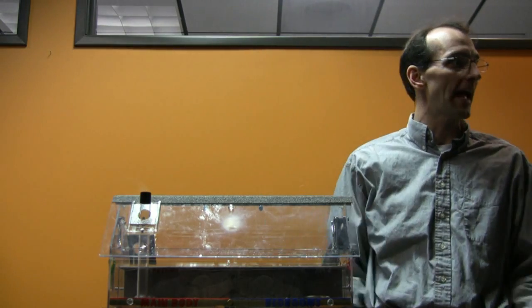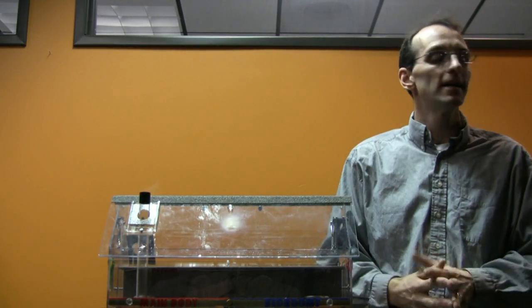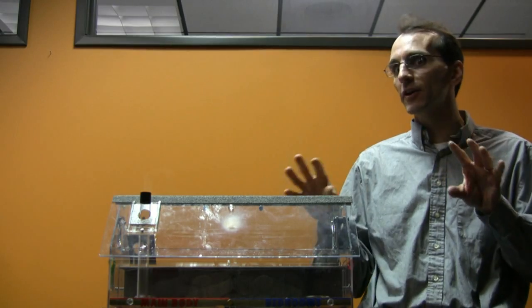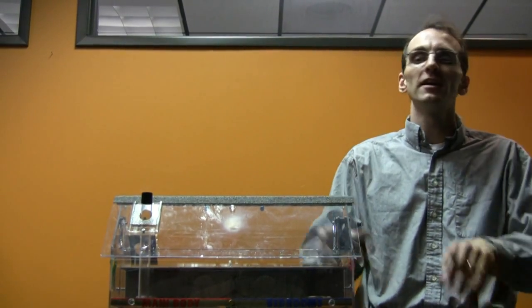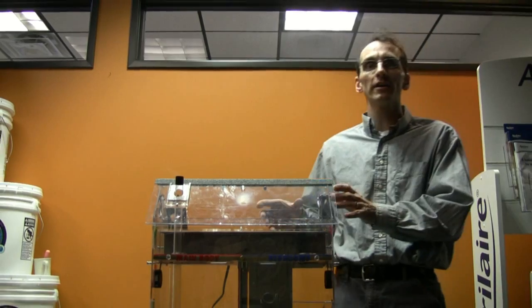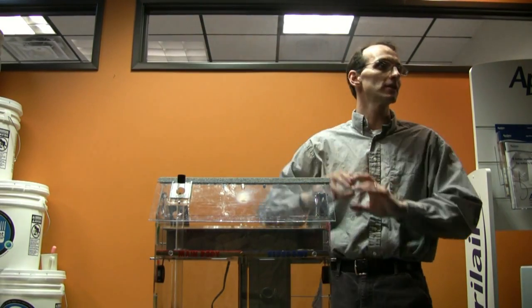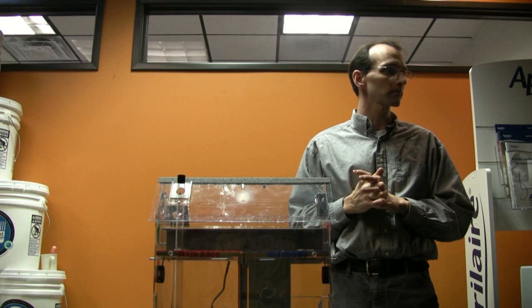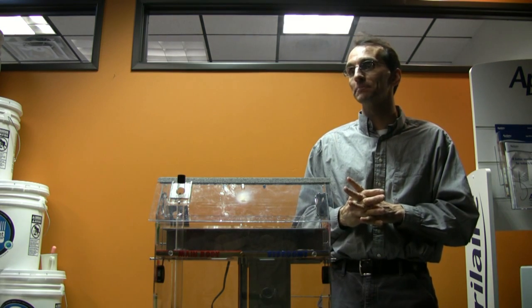That's what natural draft chimneys do. A typical scenario where you might say, oh, this could be trouble, is you have your old naturally ventilated water heater next to the brand new high efficiency furnace, and the old water heater's exhaust goes up and attaches to maybe a 6-inch metal flue. That is a big warning sign right there.